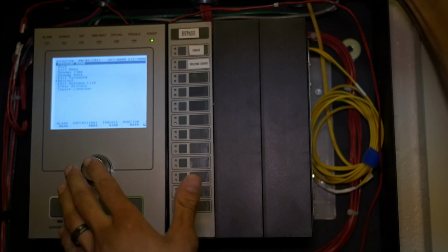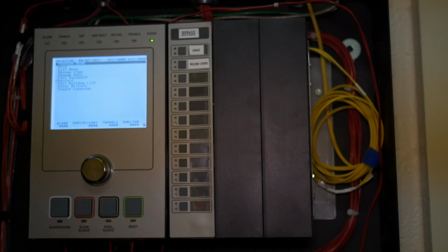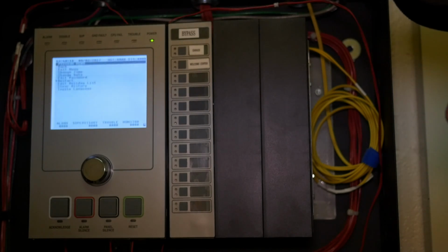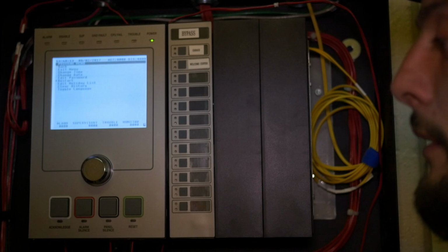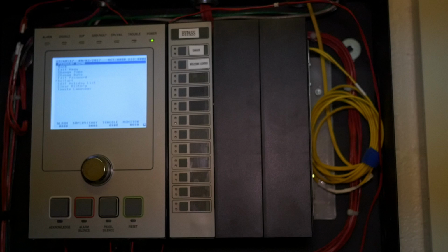A restart will basically entirely drop power to this thing for a second and restart the whole system, and that will actually take off any disables you had, any enables, or anything that was on the panel is going to be back to normal. It's going to restore back to completely as if it was never touched. So restarting the panel and resetting are a little bit different. Restarting is if we had devices disabled, and instead of going through and individually enabling them, you would just come and restart the panel, and that would bring all those devices back up.